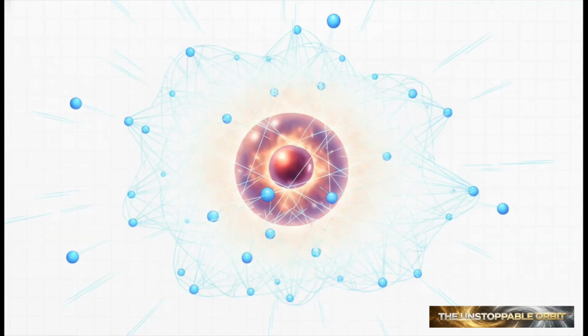And the result here is absolutely huge. As the fuel heats up, that wider net means the uranium-238 starts gobbling up more neutrons without actually fissioning. This causes an immediate drop in what we call the resonance escape probability. Basically, fewer neutrons escape the trap to go cause the next generation of fissions, so the reaction is instantly starved. Boom! It's an immediate, unbeatable physical brake on the reactor.